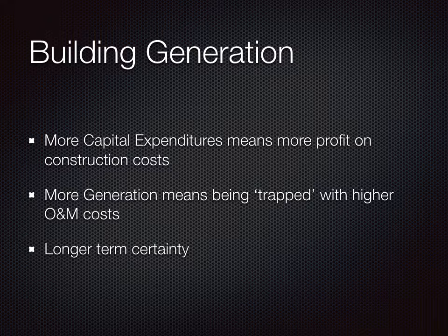Now, going back to the previous slide, why I mentioned public opinion: your choice in building generation varies heavily with public opinion as well as fuel type. Currently, we have a market that favors natural gas generation, and coal and other fossil fuels are on the way out, as is nuclear power, due to the customers not liking those forms of power because of bad publicity and environmental impact. As a result, a utility may be of the opinion that building solar is good. However, this comes to a balance with regard to reliability of the greater transmission grid, as solar does not support the well-being of the grid as well as other options.